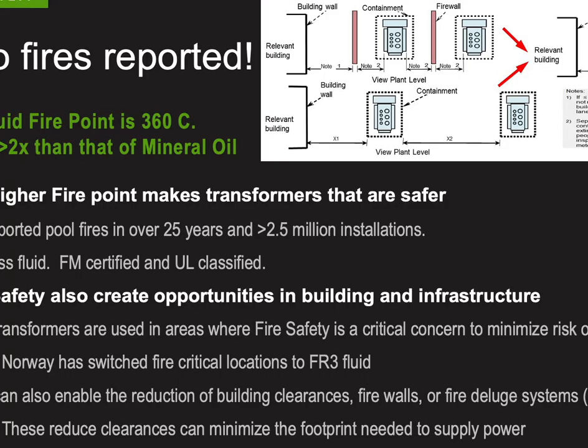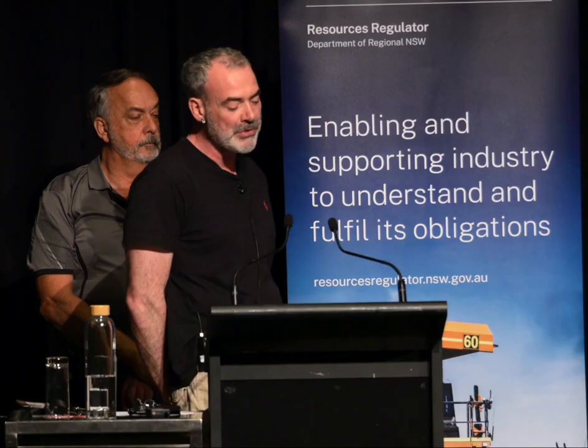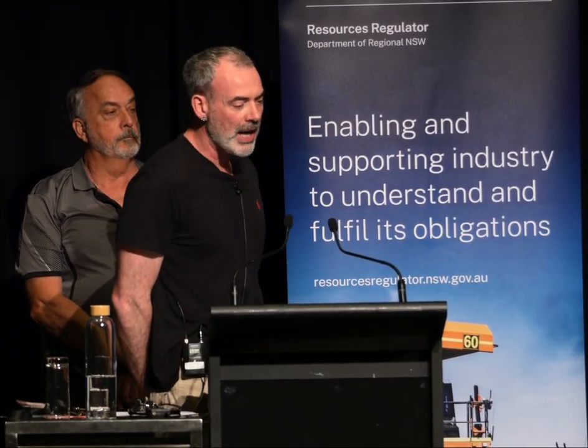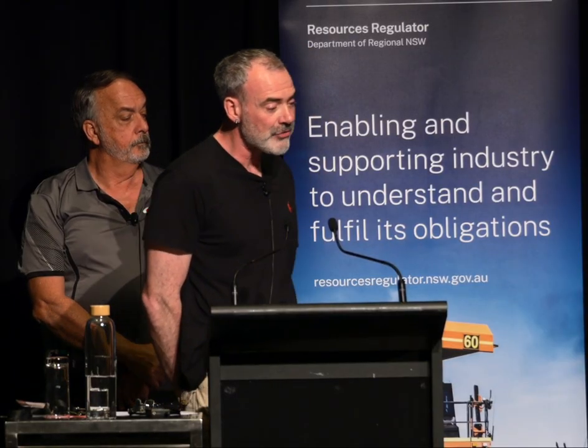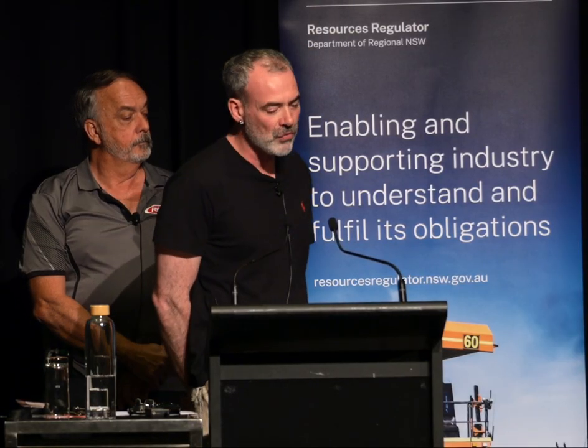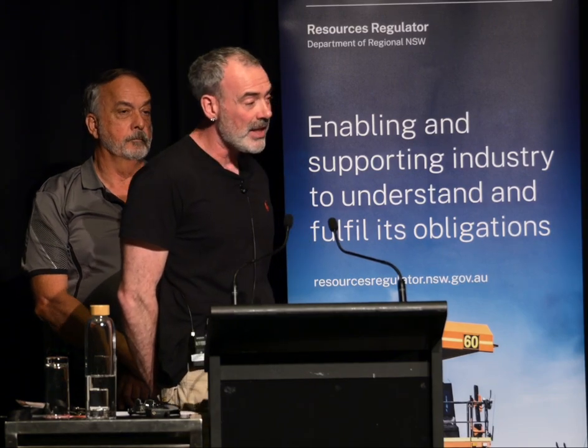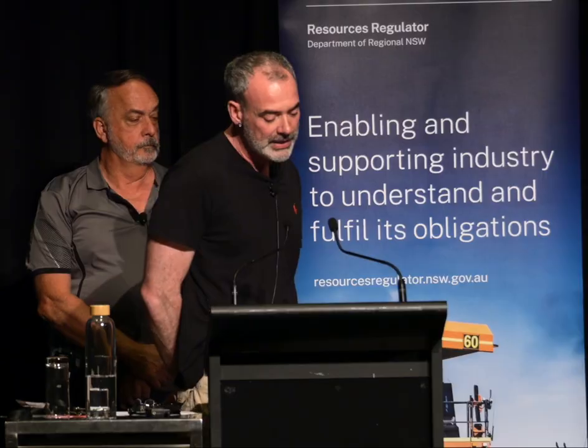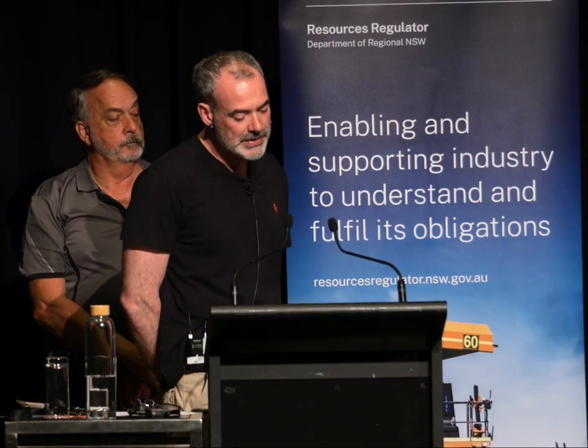So just continuing on the theme of fire mitigation, for those ester fluid-filled transformers that you operate, the risk of fire is lower because the fire and the flash points of the ester fluids are higher than mineral oil. So the fire point of natural ester is the highest, 360 degrees Celsius. That's 200 degrees Celsius higher than mineral oil and about 45 degrees Celsius higher than synthetic ester. We've not had any reported fires of FR3, our natural ester, in 25 years of use in transformers. Ester fluids are called K-class fluids, so that's low flammability. You might have heard of that. They're approved for use by FM Global and others.